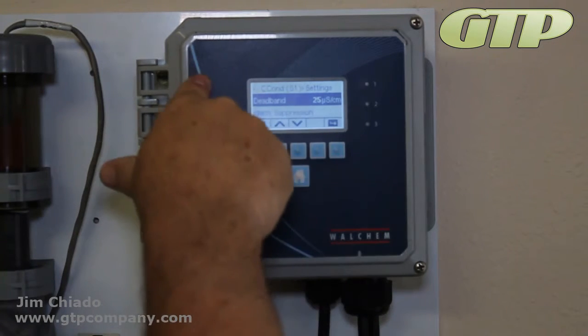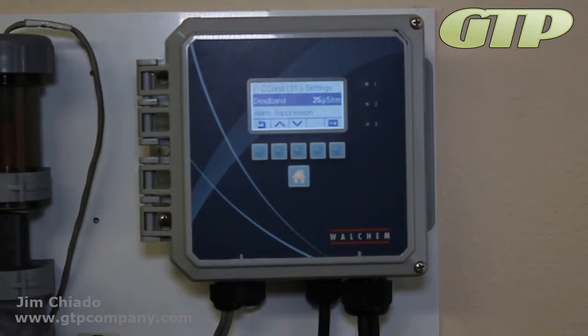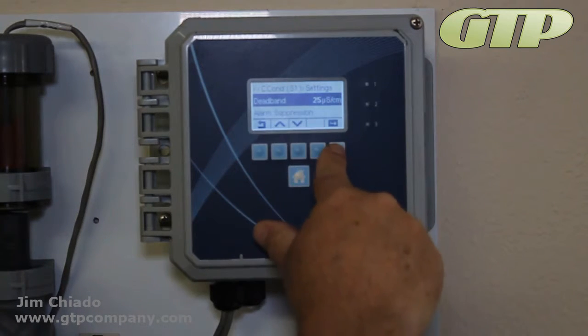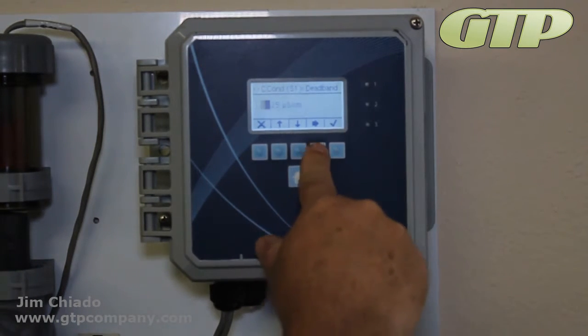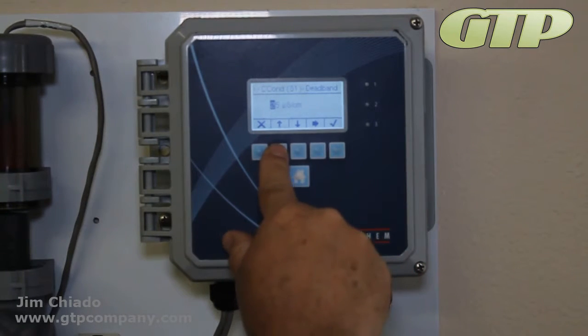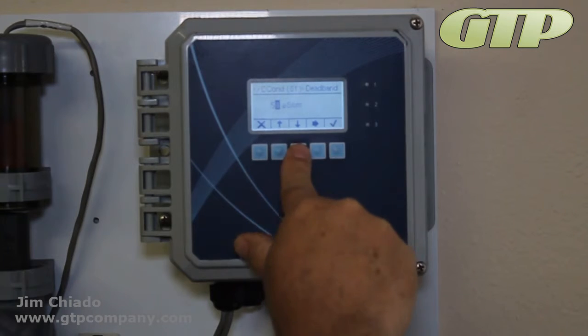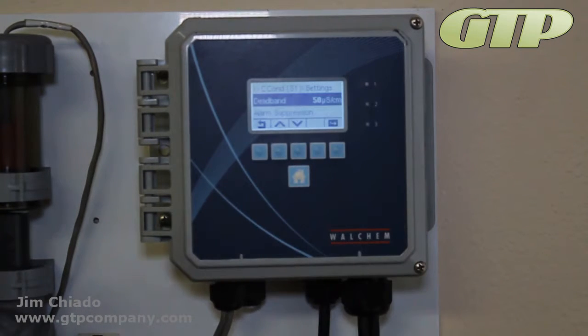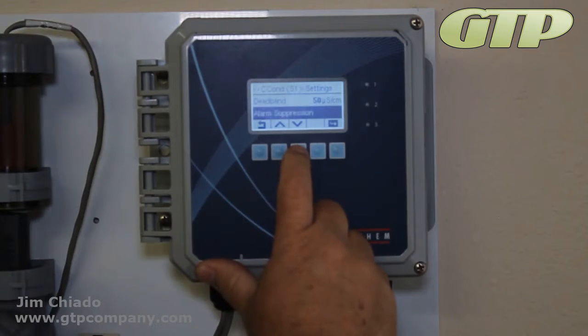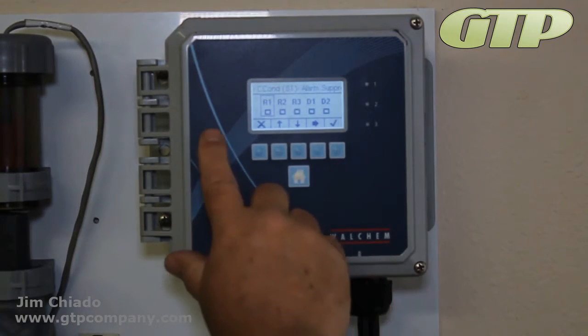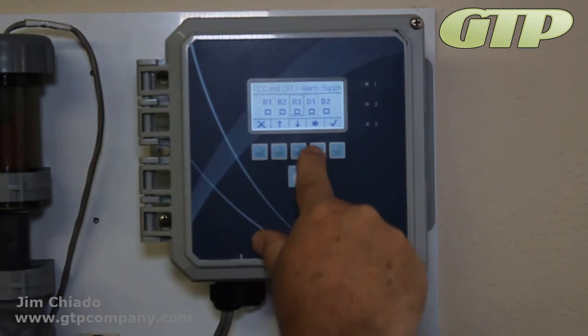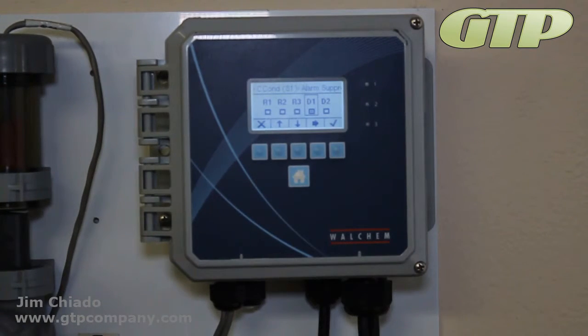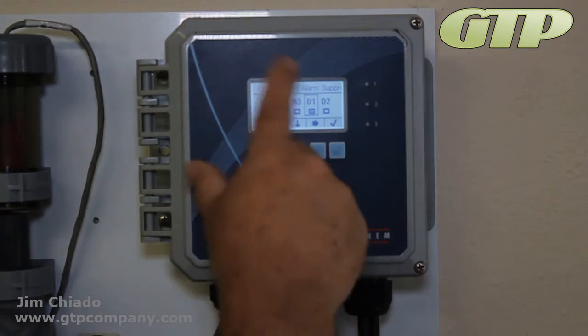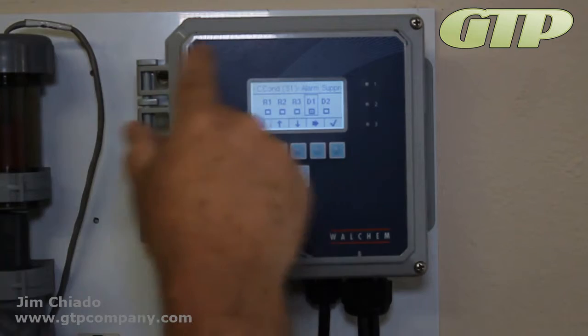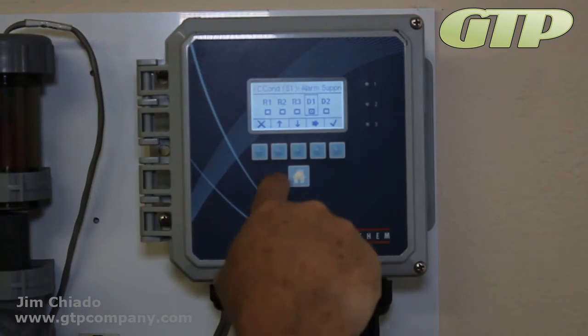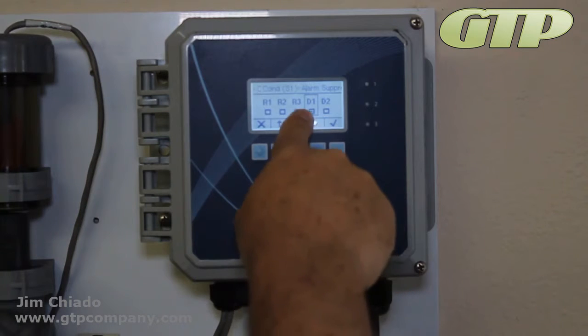Deadband. This deadband is based on those alarms going off, just like you have for your deadband on your bleed. Now the deadband at 25 is kind of small. You can leave it there. Again, this is a user preference. We'll say 50 microsiemens, just so you can see it. Alarm suppression: you can suppress the alarm if the D1 is on. If it's in no flow and, say, it drains out or something like that, you suppress the alarm if there's no flow. As long as there's flow and those first two have alarms, go ahead and tell me. Okay, I like to leave that one on.